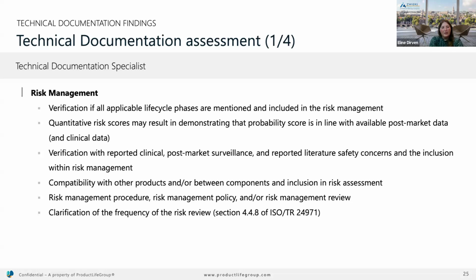Then we see a lot of focus on compatibility with other products or between the components, and whether this is really addressed in the risk assessment. So keep that in mind. Then maybe not so much related to the technical documentation, or I'm not yet fully convinced. But often we see requests for the risk management procedure, risk management policy, and or the risk management review. And this last aspect is of course new in the latest ISO 14971, and therefore included. And then, although it might be perfectly included already in your risk management plan, often they ask for some kind of additional clarification of the frequency of the risk review, which is also specifically addressed in the reference section of the ISO TR related to the 14971.